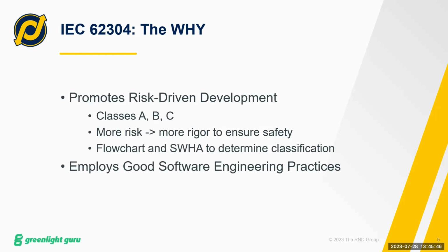So by having different software classifications, A, B, and C, like I said, you can apply less rigor and do less details to the Class A's than you do to the Class C's. So oftentimes for Class C, for software that we typically develop, will be our results processing algorithms. And so for those additional items that we have to do, we have to provide more detailed design and do more rigorous testing on that, which I think, for something as important as a results processing algorithm, you'd want to do that. In Class A, we might have some of our user management, some things like if you're just storing data, transferring data, some of those types of things would be considered Class A.